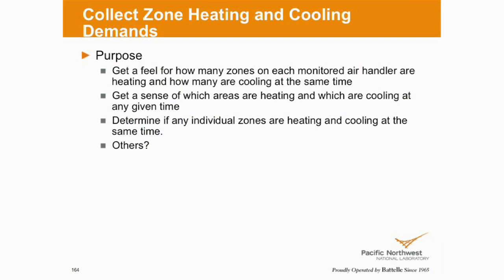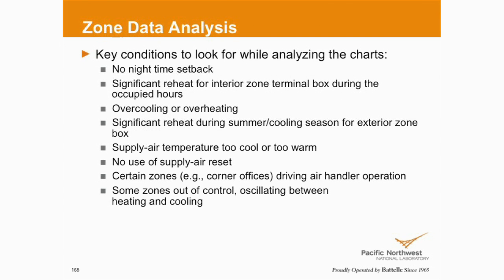So the purpose is that we want to collect some information for the terminal box. We want to see if the terminal box has a nighttime setback or not. We also want to know if there's significant reheat by monitoring the reheat valve position. And we have the zone temperature and also the zone temperature set point. We compare these two parameters so we can see if the zone is overcooling or overheating.